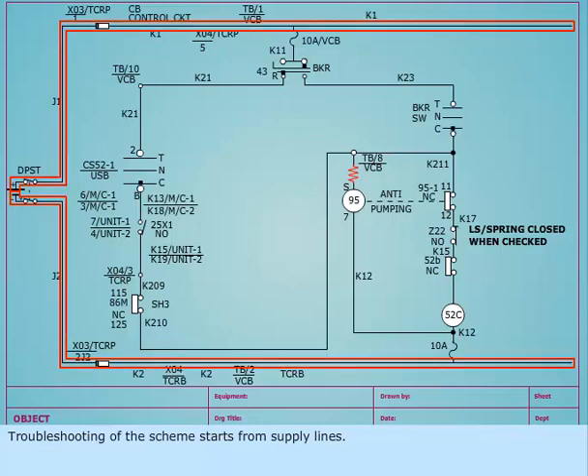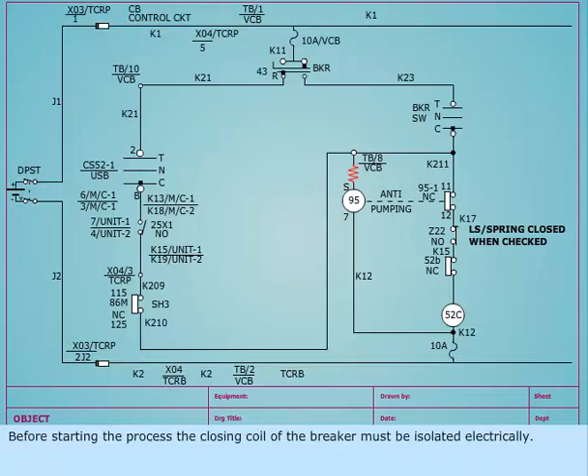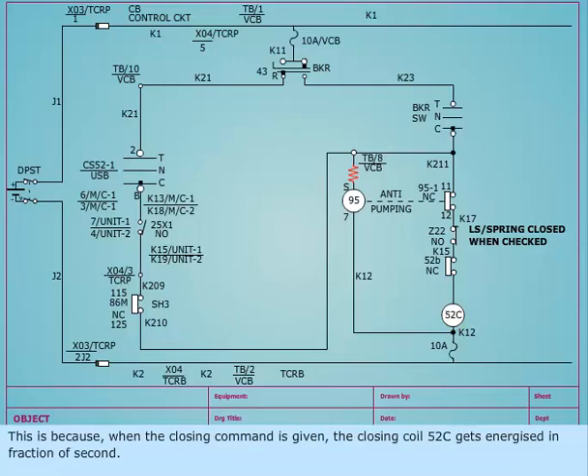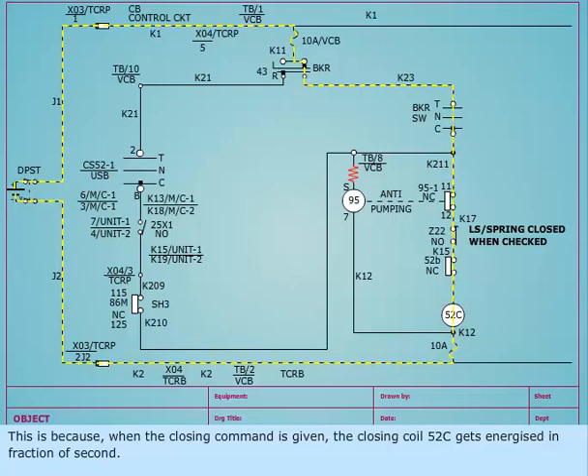Troubleshooting of the scheme starts from supply lines. Before starting the process, the closing coil of the breaker must be isolated electrically. This is because when closing command is given, the closing coil 52C gets energized in a fraction of a second.